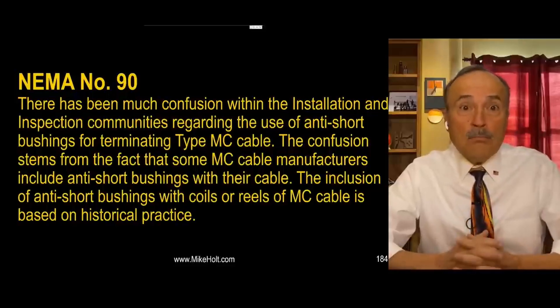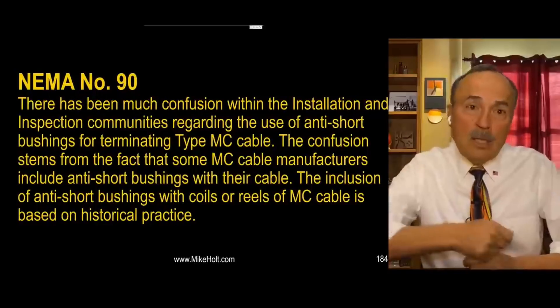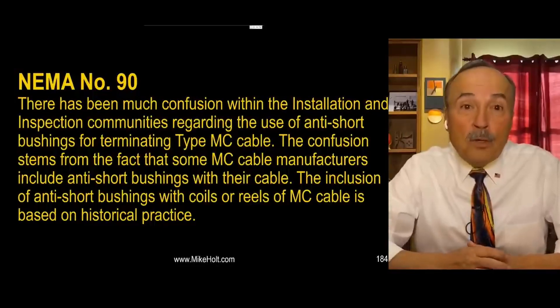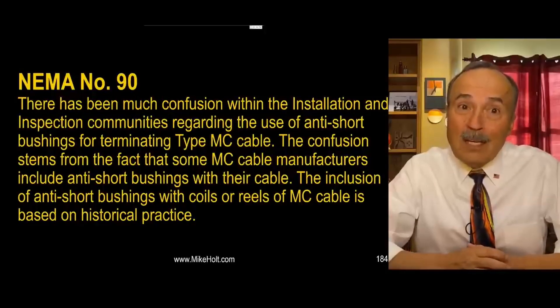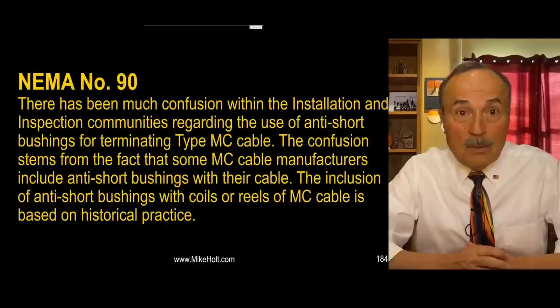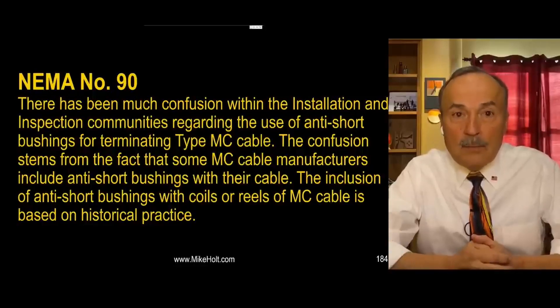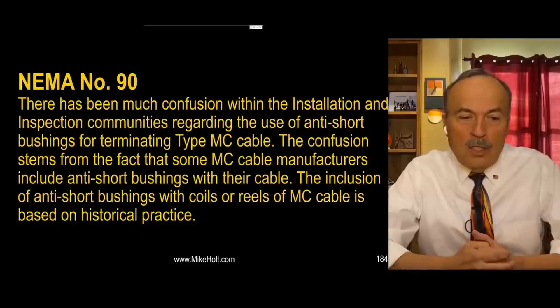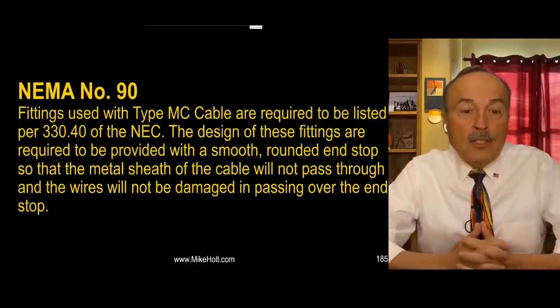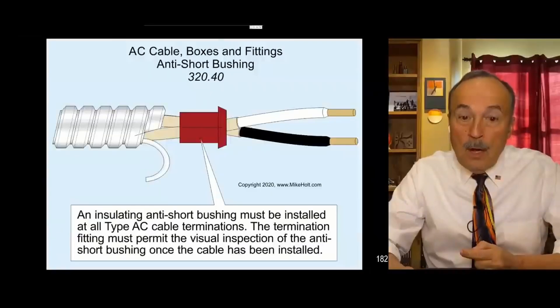A guy who actually reads the code and reads NEMA bulletins knows what's going on, doesn't put anti-short bushings in - because the fitting for MC cable was never designed to use them. If you do put an anti-short bushing in, you're probably violating the code, because NEC 110.3(B) says you have to install it according to the instructions, and the instructions don't include anti-short bushings for MC cable.